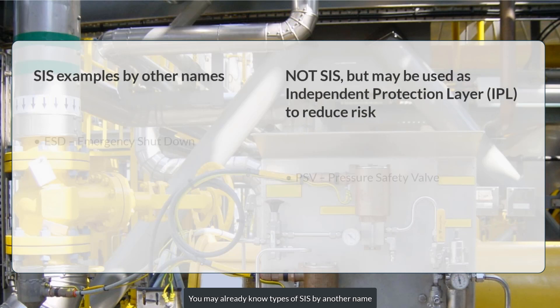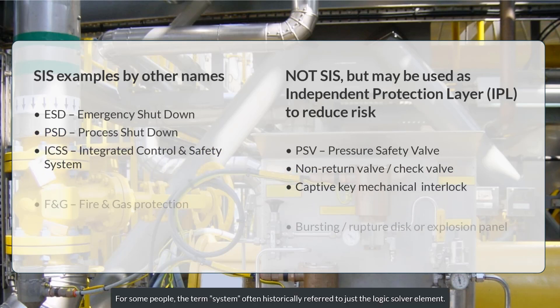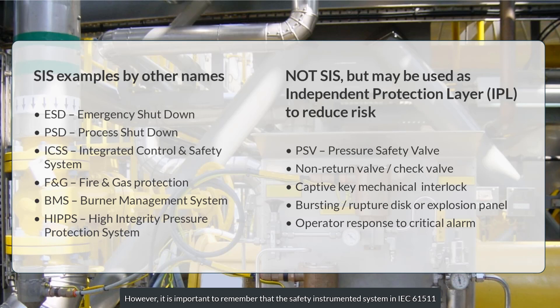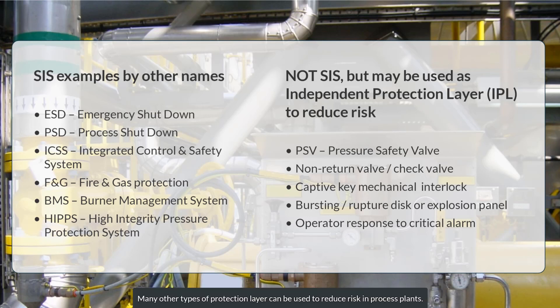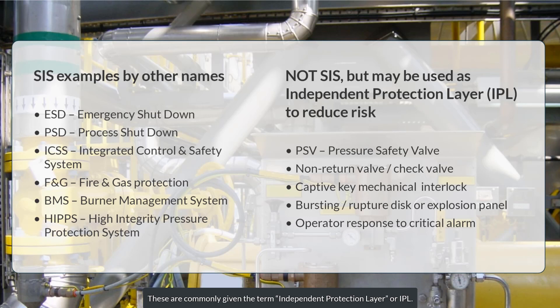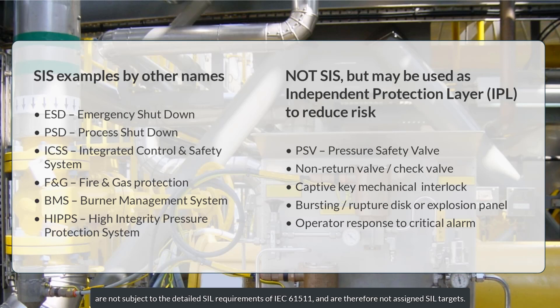You may already know types of SIS by another name, such as the examples shown here. For some people the term system often historically referred to just the logic solver element. However, it's important to remember that the safety instrumented system in IEC 61511 includes all the field equipment as well as the logic solvers. Many other types of protection layer can be used to reduce risk in process plants, commonly given the term independent protection layer or IPL. A SIF is one form of IPL that uses instrumentation. Non-instrumented IPLs such as mechanical relief valves are not subject to the detailed SIL requirements of IEC 61511 and are therefore not assigned SIL targets.